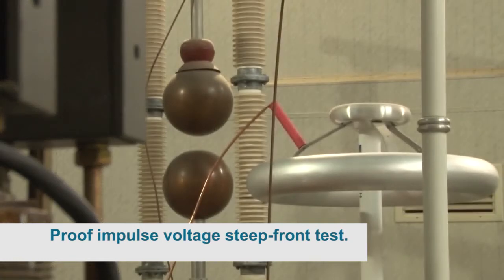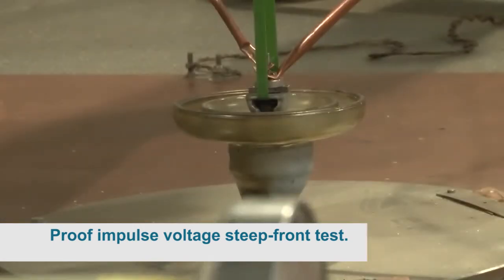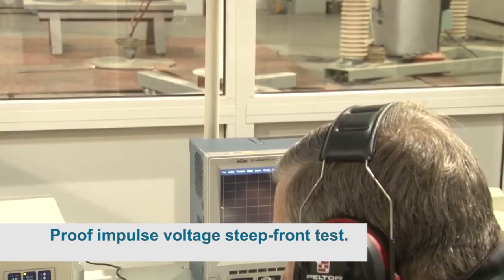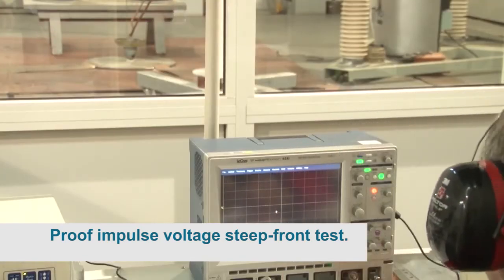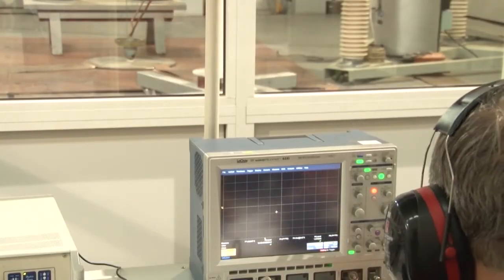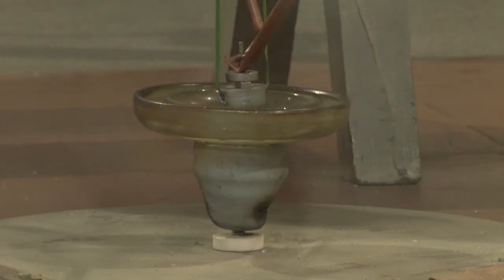Proof impulse voltage steep front test. Verification of proof of insulators of type PS12A and PS70E under the impulse voltage steep front. Wave steepness is greater than or equal to 2000 kilovolts per microsecond. 10 impulses of positive and negative polarity. Insulators meet the IEC requirements.